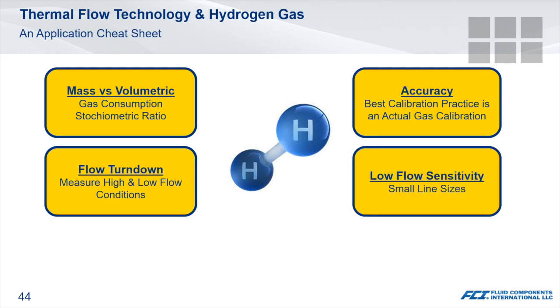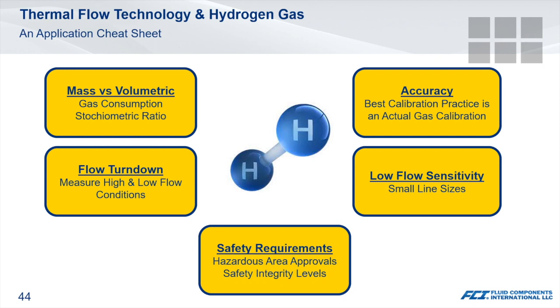Don't give up on low flow ranges that fall within the Reynolds number transitional zone. Solutions exist for accurate measurement. When multiple technologies are suitable, select instruments that will meet site-specific safety requirements and carry the proper pedigrees.